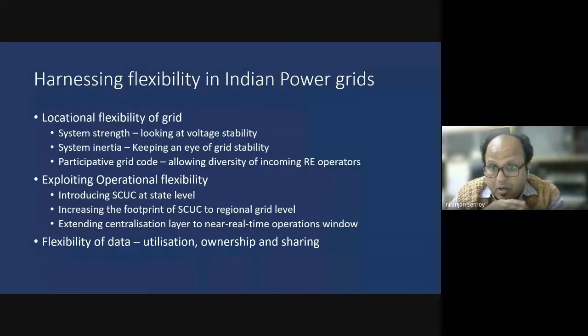Of course, you must remember that in India, we need to have a universal grid code. We need to have one grid code for the entire country. You cannot have different grid codes in different parts of the country, even though the grid flexibility is not the same throughout the country. Depending on the system strength, the voltage, the X by R ratio of the connected network, and the connected generation levels, the ability of an independent power producer to influence the system voltage by injecting reactive power may vary significantly. So the way the universal grid code is to be implemented at a location may differ.